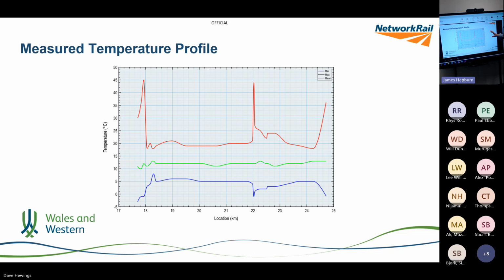Could we do something with that data to explore the idea we looked at? That characteristic is an interpolated view from those points. We haven't got points all the way along the tunnel, but we know where every structure is - locations of every one of the 1400 structures. So if we take into account the peaks, and we know where there are measurement points that are much lower, could you interpolate a curve that's the best fit on the data we have and see what that does? In parallel, we started some new temperature monitoring, ongoing, to get a whole new set of data over the whole year that will produce a much better version of that.